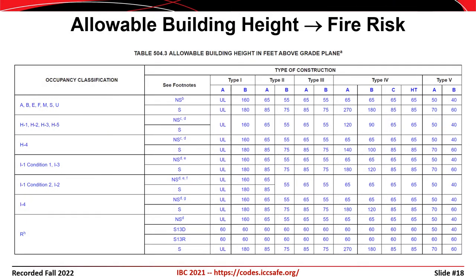Table 504.3 of the International Building Code provides the maximum height of buildings based on the occupancy classification and the type of construction used. In this table, NS means not sprinklered, S means sprinklered, and UL means unlimited. The height of the structure is important in this context because as the height increases, it takes longer for occupants to evacuate and it becomes more challenging for firefighters to extinguish the fire. As a result, buildings that are more flammable or that aren't required to have sprinkler systems are generally restricted to lower heights than buildings constructed of non-combustible materials or buildings that have active fire suppression systems.